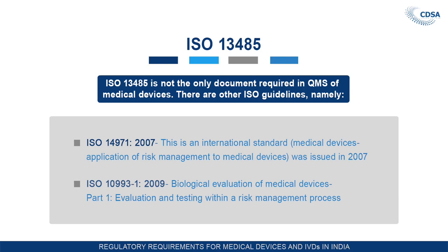Now, what are the other ISOs required under this umbrella of 13485? You require ISO 14971, an international standard that ISO issued in 2007. The title is Medical Devices, Application of Risk Management System. So risk management is covered under ISO 14971. In case you want to address a risk in the whole process, this will apply and guide you to manage that risk.